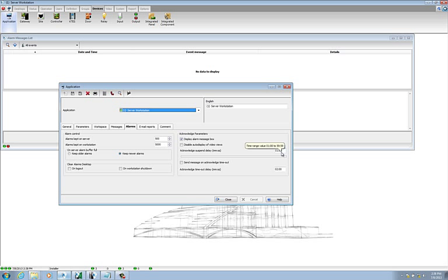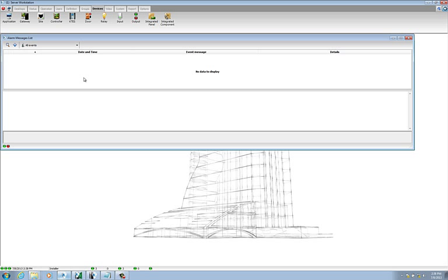If I don't want to acknowledge the alarm right now, I can click on suspend, and a minute afterwards it's going to pop up again to be acknowledged. This is defined, and those can be changed, from 1 minute to 60 minutes, and same thing for the suspend delay, from 1 minute to 60 minutes also.